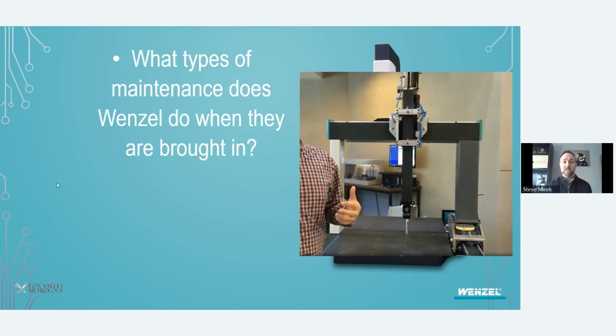So with every calibration, what we do is we go through the checklist and we remove the machine covers and we clean all of the drive surfaces, the rails, and the motors. We clean and realign the scales and the reader heads.